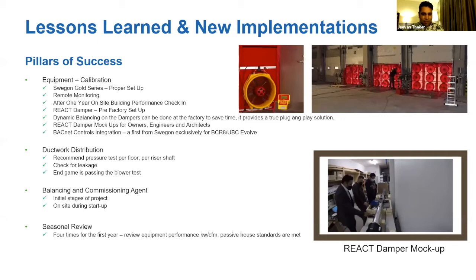Second part is balancing and commissioning. Again, no fault to anybody. It's making sure you have the proper balancing and commissioning agent who has done a Passive House or is getting trained to do Passive House, because you need to have the right equipment. We had some commissioning issues on the project, and we ended up jumping in to help out because it was an equipment question. It's easy, when things don't work, to point first to the equipment, because maybe the unit's not producing the right air. Maybe it's engineering. Maybe the static pressure is wrong. But with balancing and commissioning, ductwork tightness is a big part of it.